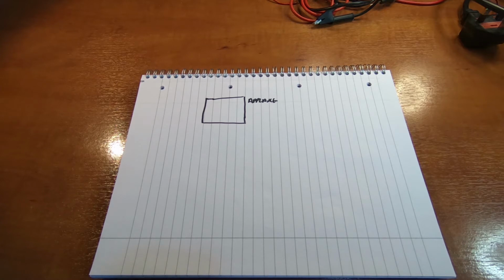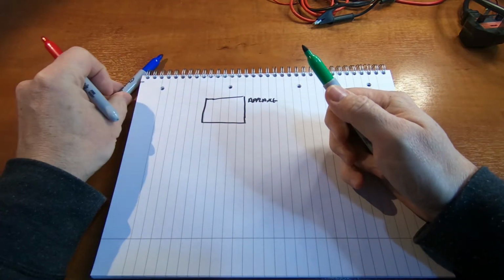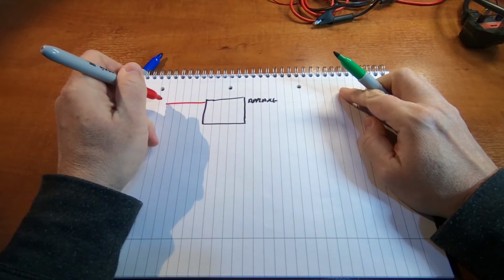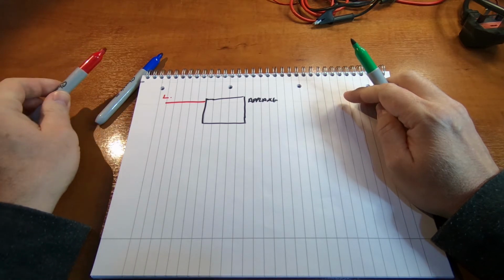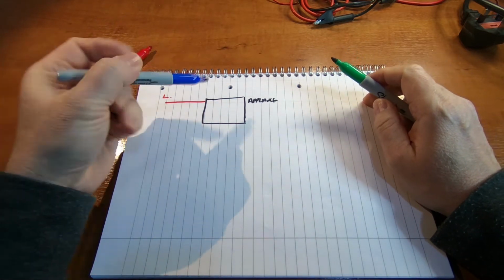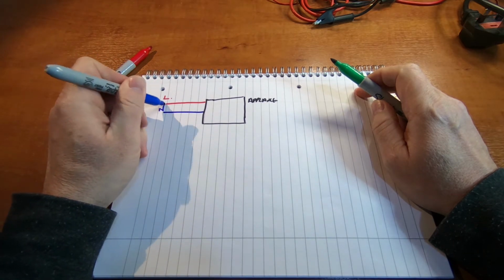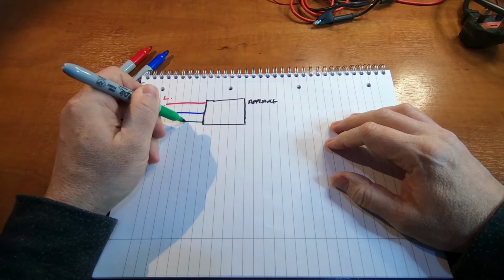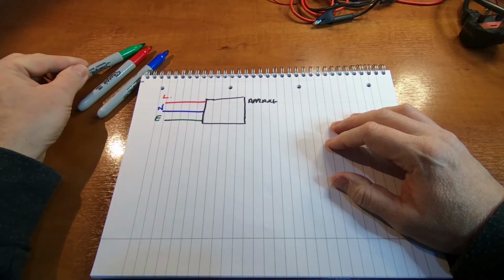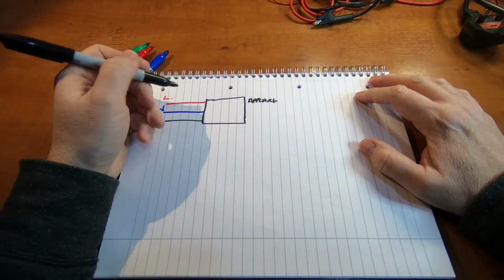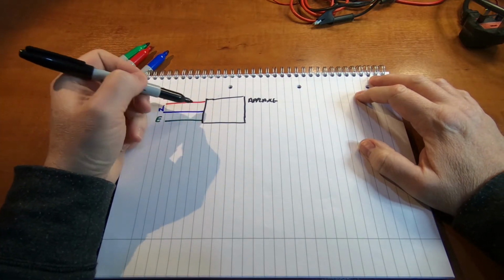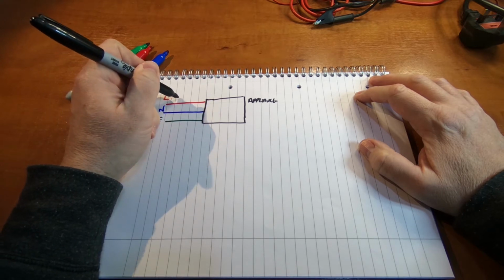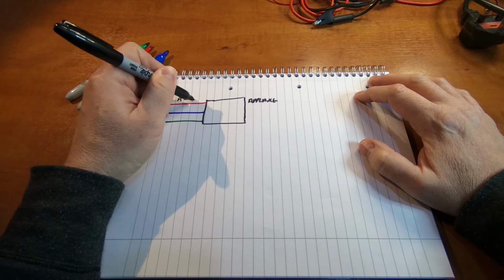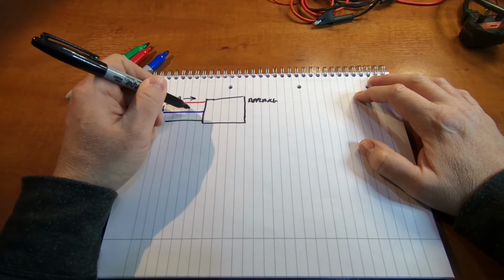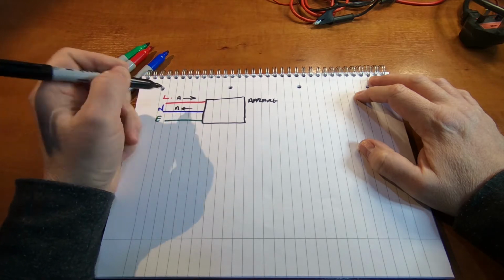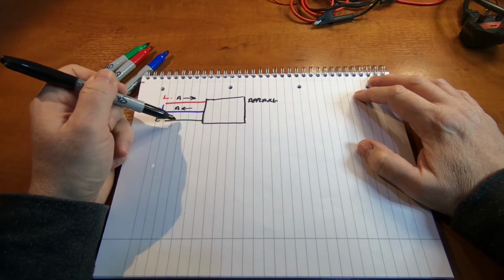So let's just get some different colours here. If we have our three lines coming in, we've got our live, and this is mains voltage. So in the UK it's 240 volts, and then we have our neutral line, and then we have our earth. Okay, so the way that current works, what should happen in a correct appliance is that all of the current coming in, so I'll mark that as an A, current coming in should equal the current coming out on the neutral line, and there shouldn't be any current happening on the earth line.